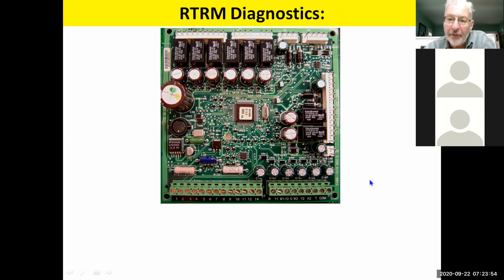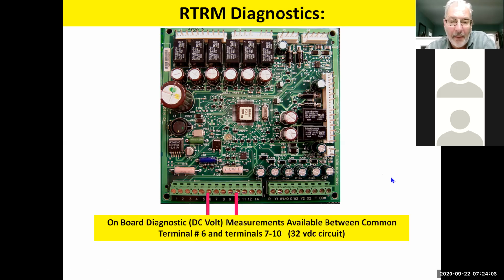There are some diagnostics. So when you get to the rooftop, and if it's locked out and you're not sure what's going on, don't reset the power initially. Okay, what you want to do is go to this terminal strip right here. Even if there's wires on or if there's no wires on, whether it's a communication board, a Trane board or just a plain conventional thermostat, there are diagnostics available right here. Terminal 6 is going to be our common, 7 is going to be our heating diagnostic, and 8 is going to be our cooling diagnostic.